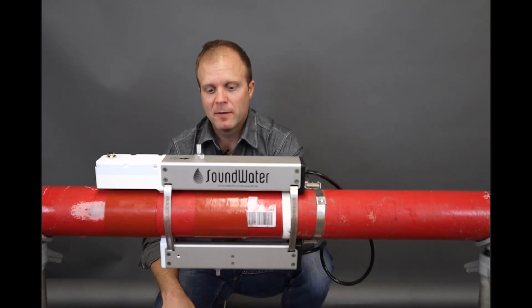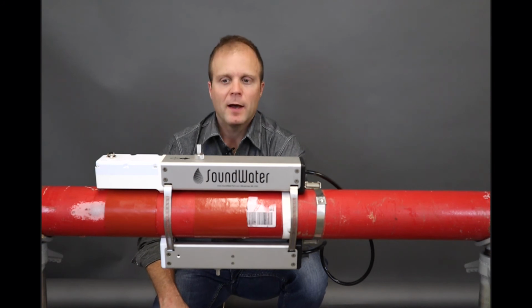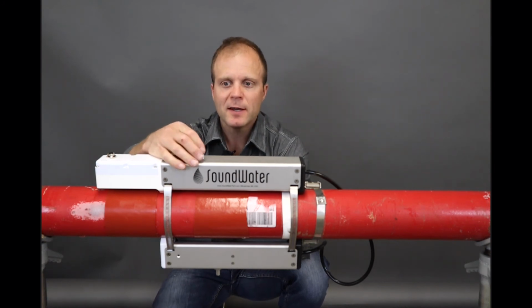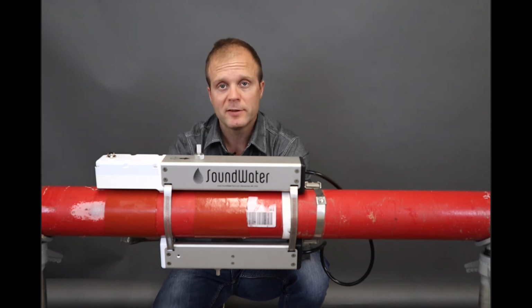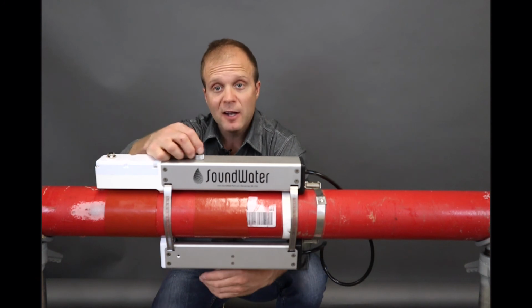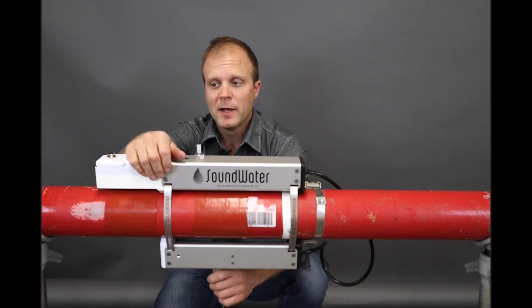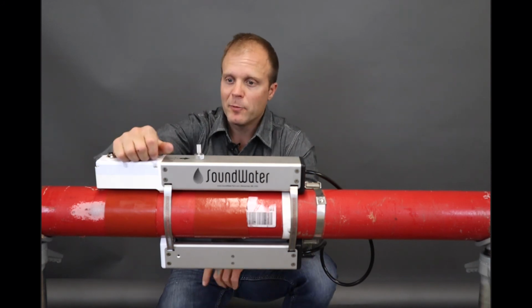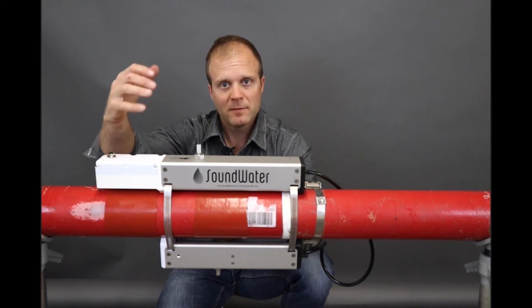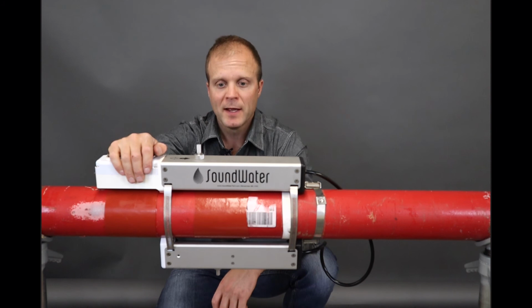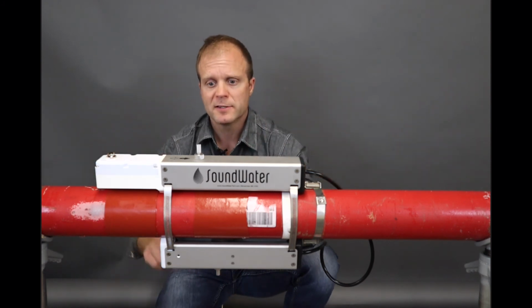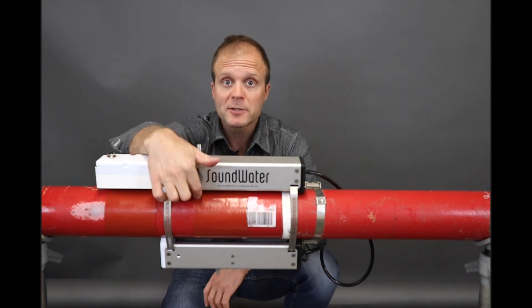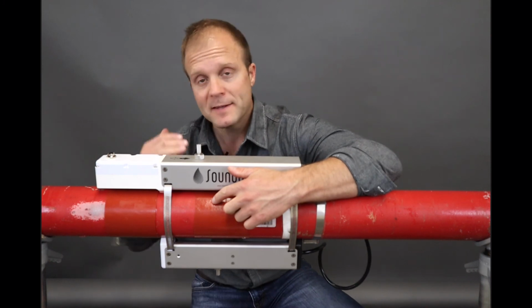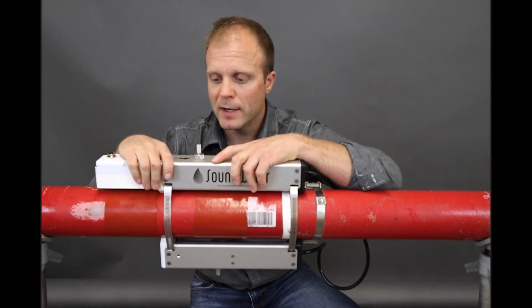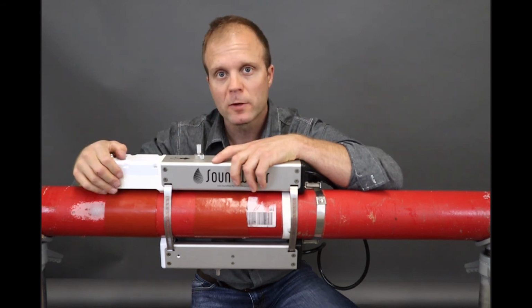And that is sufficient. Okay, in this case, does more pressure help? No, to some extent. You want it nice and snug initially. If it's not nice and snug, it's kind of rattling around. Yeah, it won't work too well. The sound won't be able to couple into the pipe. But once it's snug, if I were to get a wrench and really crank down here, it's not going to help the meter do its job. So nice and snug. You might get some pliers and just do a quarter turn or so just to make some tension so the system here is loaded mechanically, and then over time and thermal variations, it's not going to loosen up. But don't overdo it. If you overdo it, you can rupture the coupling pad that's on the pipe, and then the sound won't be able to couple well into the fluid. So hand tight, maybe just quarter turn, half turn with a wrench after that.